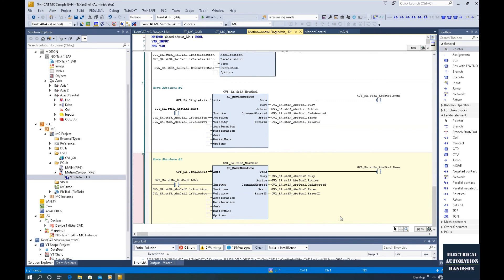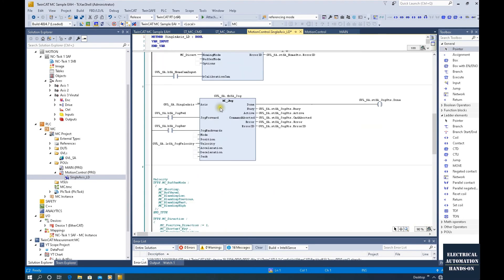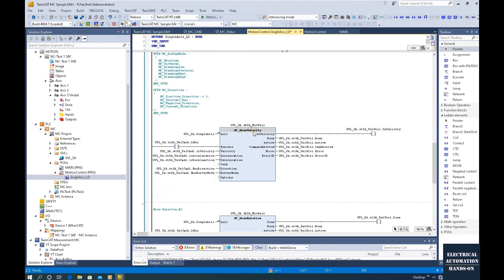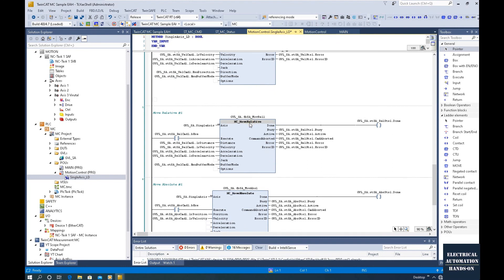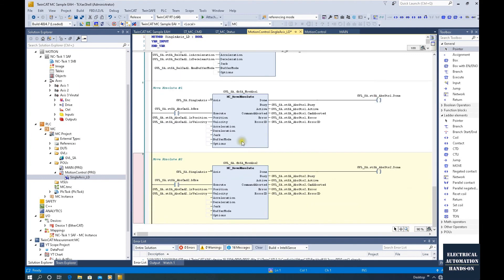We've finished programming these three typical motion commands. Let's quickly review. First, from the previous video we have MC jog. Then move velocity — using this command we can run speed control to control the axis. Move relative is the relative motion: every time we trigger this motion command, it will control our axis to run a certain distance with the velocity setting. Most commonly, we will use move absolute — here I prepared two, so for different position controls we can set different positions and velocities. Every time we trigger this using a rising edge, the command will control the axis towards the target position.